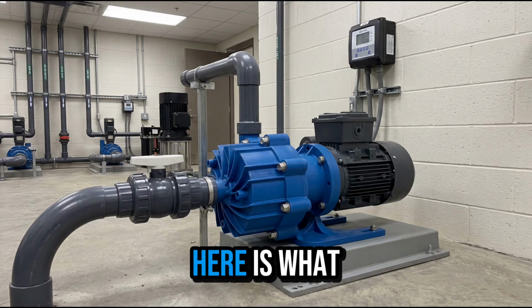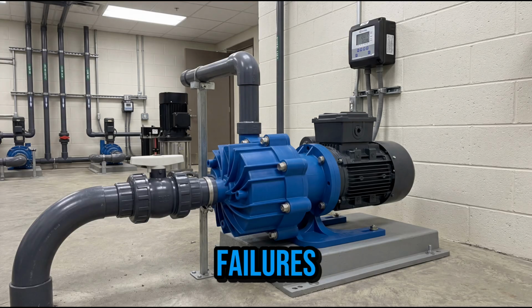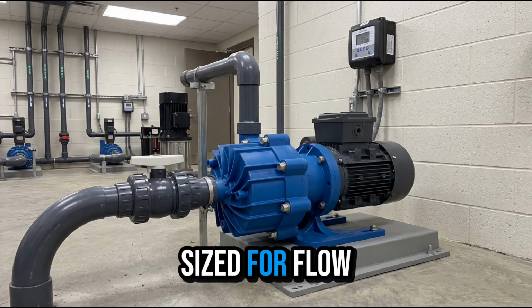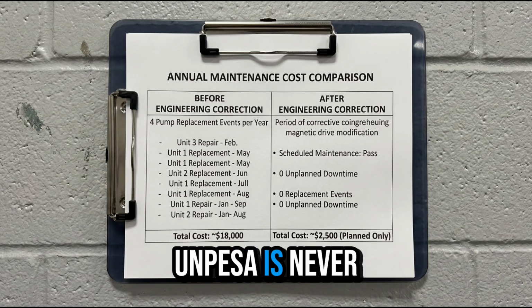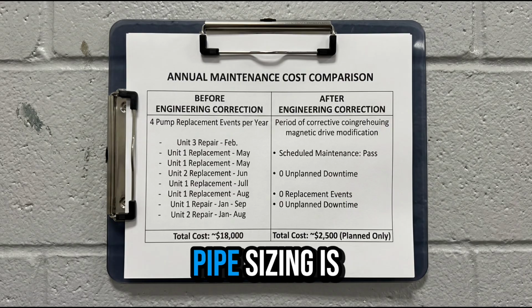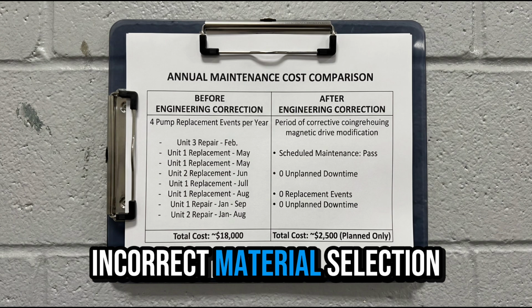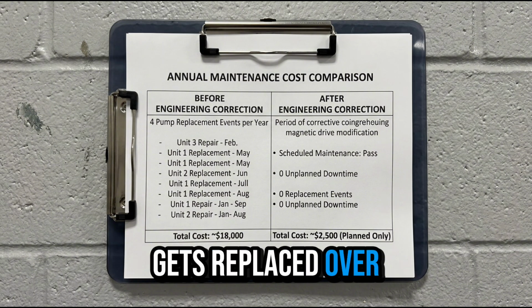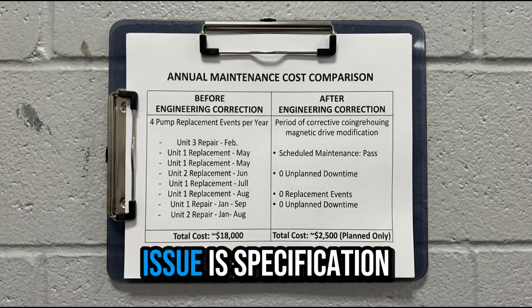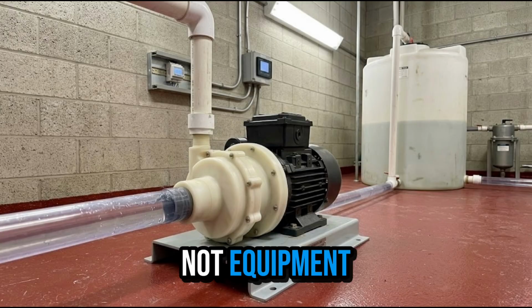Here is what happens in repeat failures. The pump is sized for flow only. NPSHa is never calculated. Suction layout is ignored. Pipe sizing is incorrect. Material selection is wrong. Protection systems are skipped. Then the pump gets replaced over and over, and the manufacturer gets blamed. But the real issue is specification, not equipment.